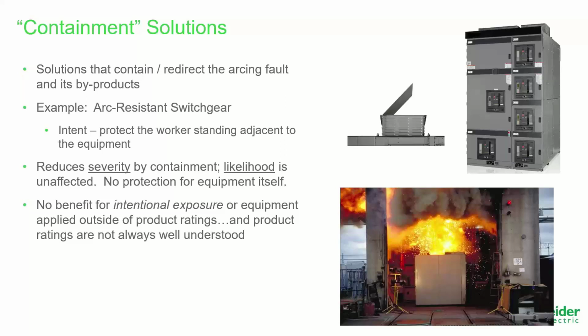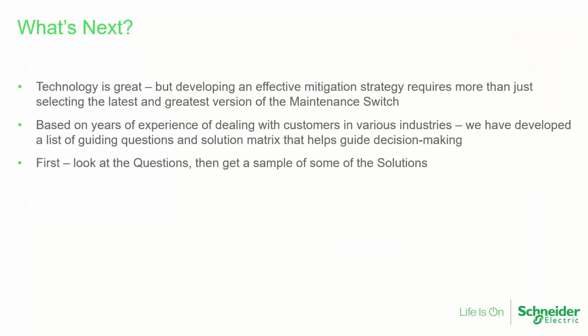The reason that you're there at that kind of incident energy level is because you have a clearing time of greater than half a second. And so you're going to have to do mitigation at that location before you can successfully apply arc resistant switchgear, something that gets kind of lost in the shuffle sometimes as we look at that. But in the right situation, very effective solution that can be used either by itself or in conjunction with some of these other things that we talked about.